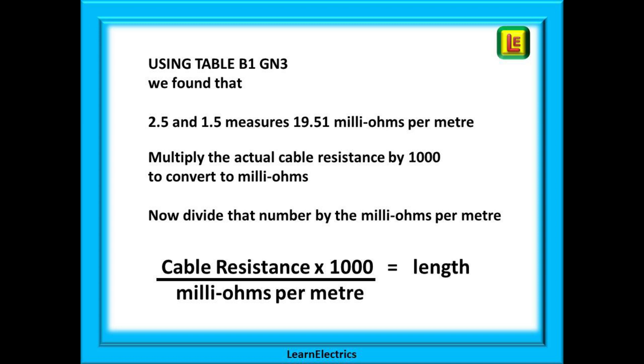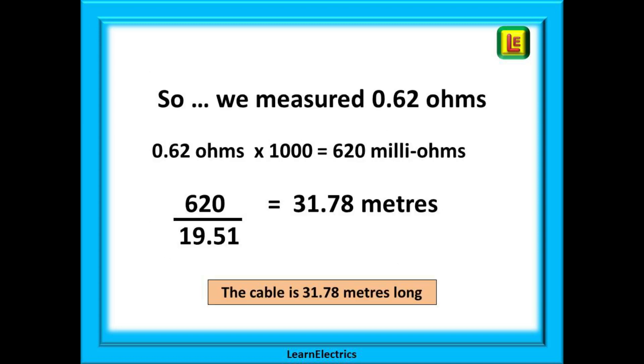This little equation shown here tells you what we are doing. Putting that into practice then we measured 0.62 ohms multiply that by 1000 and we get 620 milli ohms. Divide that by the 19.51 from the tables and we have 31.78 meters. The cable is 31.78 meters long. So easy.